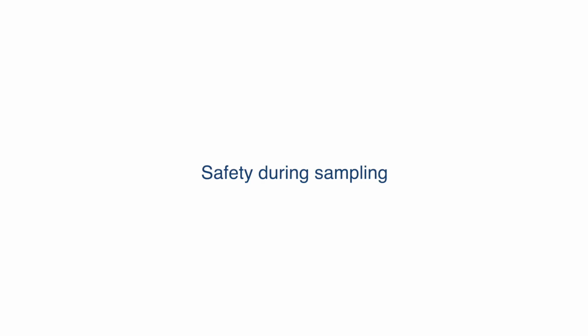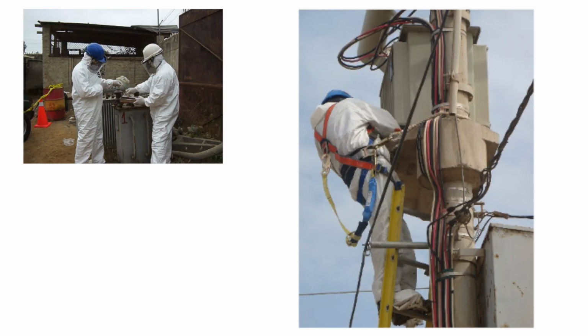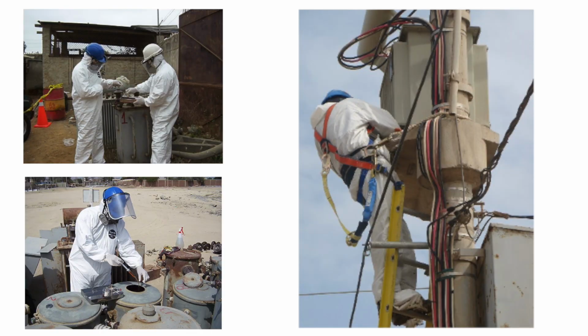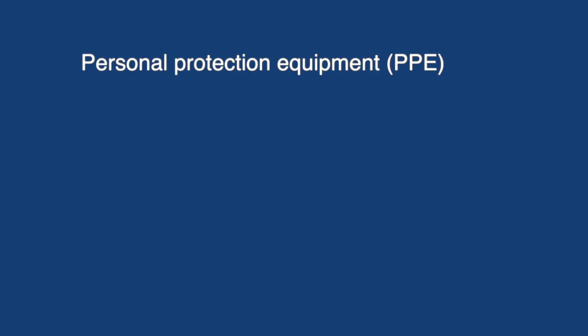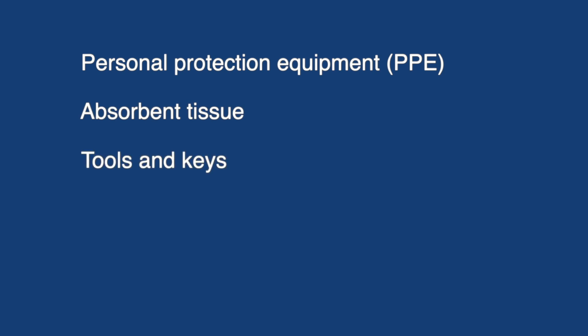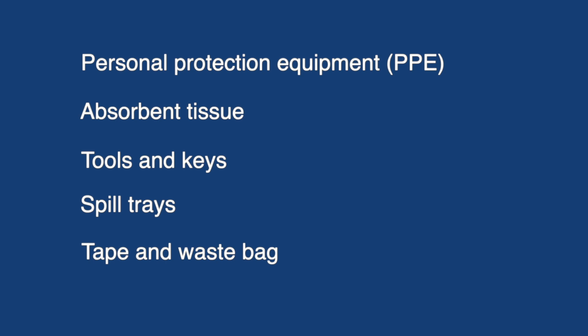During sampling, the sampling team must wear personal protection equipment and have materials and tools at hand to be prepared to contain or mitigate any small spills or leaks that may occur, such as personal protection equipment, absorbent tissue to wipe everything clean, tools and keys to remove valve stoppers, spill trays to place beneath the valves to contain leaks, tape and plastic bags to collect contaminated wastes that may be generated as a result of the procedure.